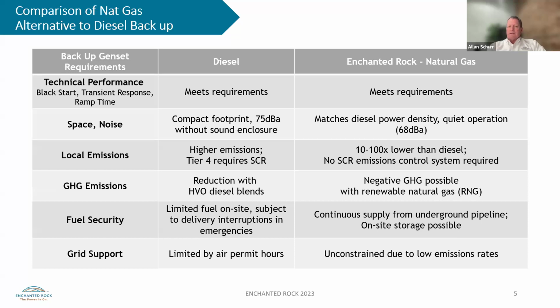We've done some interesting things in packaging our generators so that natural gas generators can match up to those diesel standards. That's not common in natural gas generation, I should point out. It's taken some extra engineering steps to do that. With that said, you get into a lot of other attributes that either are requirements or nice to have in the form of improvements over how diesel operates.